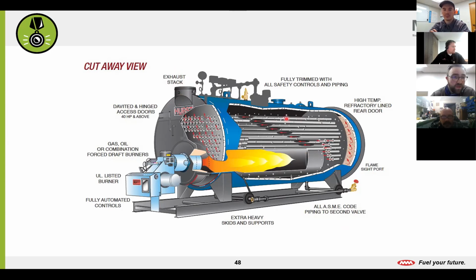And so as this flame is traveling through these tubes, the water surrounding it obviously absorbs that heat in the same way you'd see with a VRF system or a hydronic heat pump and that coil, right? The only difference is where those are, the medium is air passing through a coil. This medium is water making contact with the metal of the fire tubes and absorbing heat that way. As far as these boilers go, usually they're large, right? You get the condensing boilers. Those guys are going to be usually smaller footprints. The more traditional application that we see is going to be like those 4 units mounted in a way that allows them to stage. These guys, usually in application, you're not going to see multiple ones of these installed. It's going to be one big guy taking up space in a mechanical room, and it fires on when you want heat and kicks back off when that temperature set point is satisfied.